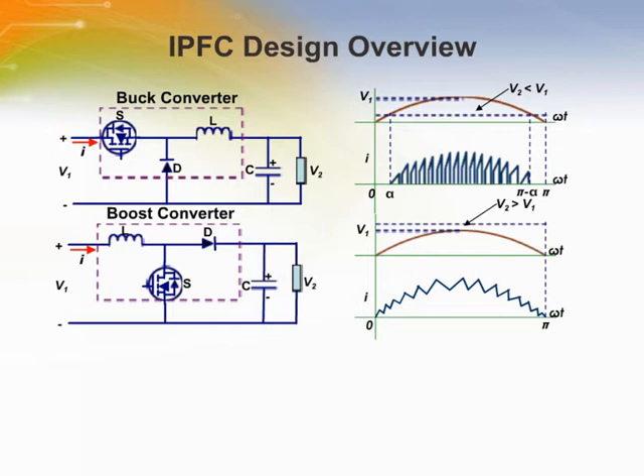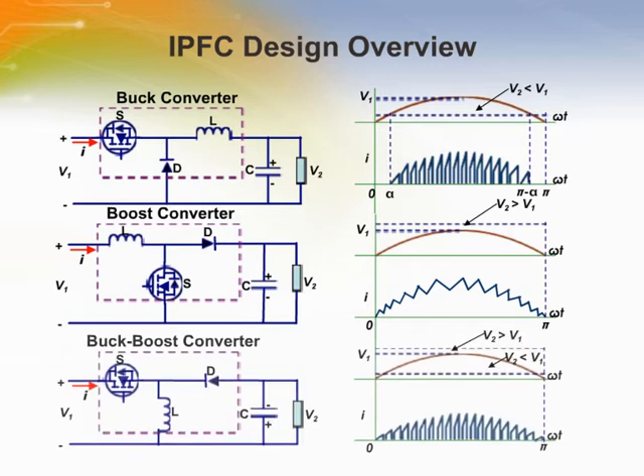For the purpose of power factor correction, the buck converter will function in discontinuous conduction mode. The boost converter has an output voltage greater than the input. When using this topology for power factor correction, the current is continuous. As shown in the current diagram, continuous conduction mode allows a continuous current through the inductor.